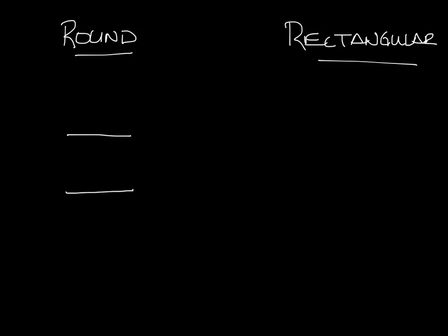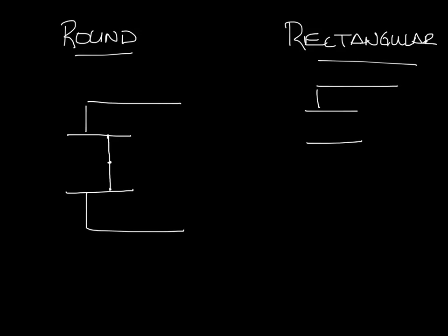So let's just draw the inlet of a single duct box inside view. The damper goes inside the inlet, there'll be a pivot point in the middle, and then you have gasketing on the end where it touches the inlet. For a rectangular, there's a couple different types. You'll have flat blades like this that pivot off of the center. And then when they're open, they kind of look like this. And then as they close, they angle off like this until they close completely and touch.